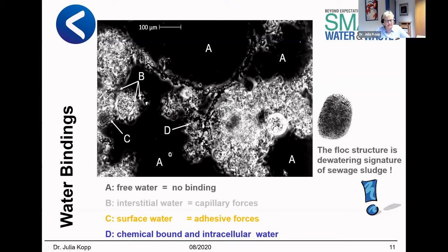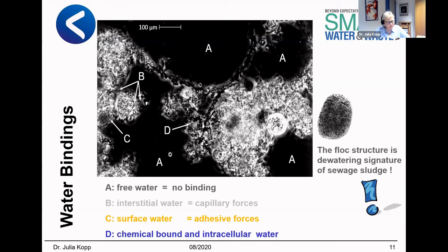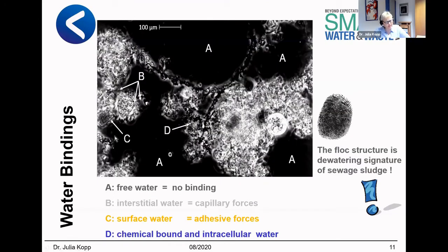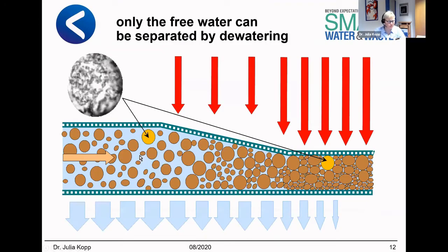The floc structure itself is the dewatering signature of a sewage sludge. We take this particle in a belt filter press to understand why only the free water can be separated. You have a belt filter press, you increase the pressure, and the particle here is the same as here. In this phase you have only particles and the water inside the sludge particles — this water will remain. Therefore, the structure of your particles describes the dewaterability itself.